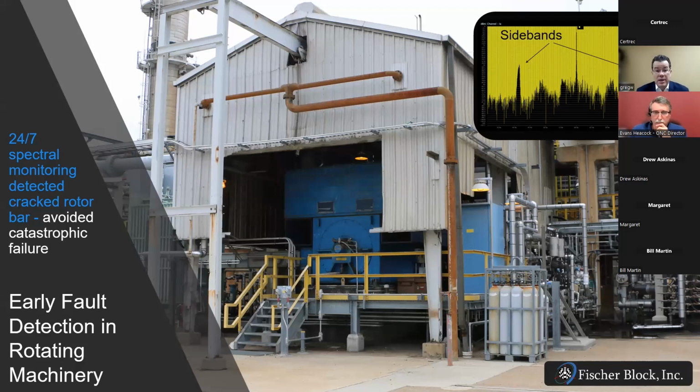So yeah, here's another case where it's rotating equipment that we're monitoring 24/7. And we have scheduled scans where the smart block device is monitoring the various loads and environmental conditions, and will do time series waveform captures and then process that data through a frequency extraction algorithm to monitor the various frequencies to ascertain the health of the subcomponents that we talked about earlier.